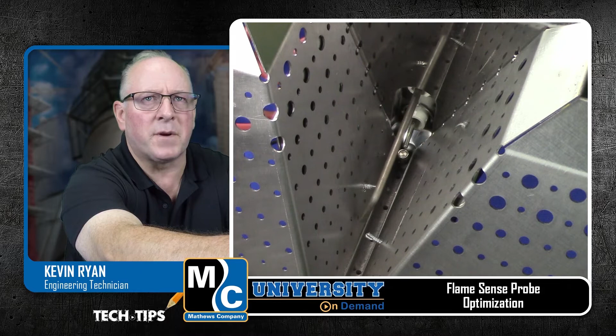What it has to see is it sends out a voltage onto the probe. It's going to go through the flame itself and then through the ground of the burner, and it creates a current loop in the ignition board to hold the flame and say that I see the flame and we can keep going.